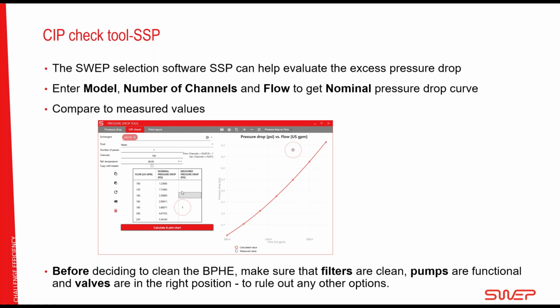And then you can enter your own measurements, and you can say plot them out and see if I'm getting inside the danger zone with more than 30% of the pressure drop compared to the nominal. And if so, yeah, you should probably talk to a cleaning in place expert to see what you can do about it.